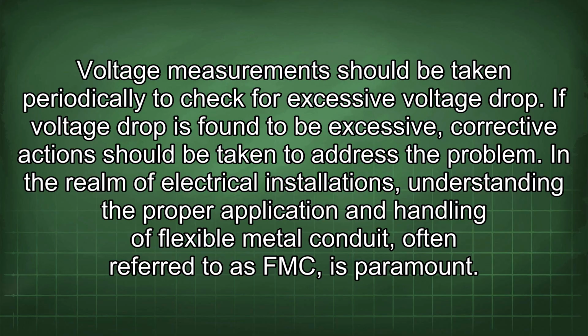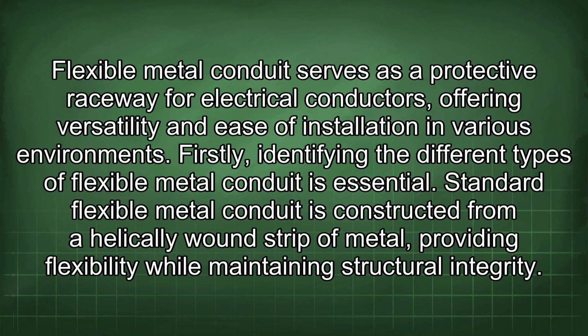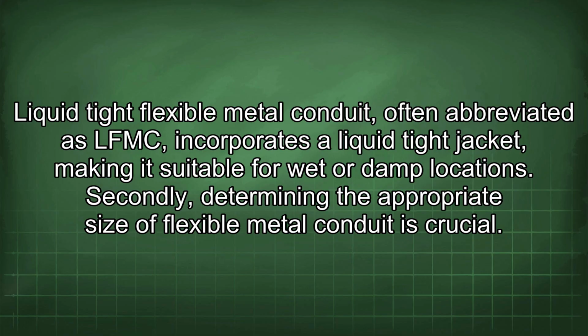In the realm of electrical installations, understanding the proper application and handling of flexible metal conduit, often referred to as FMC, is paramount. Flexible metal conduit serves as a protective raceway for electrical conductors, offering versatility and ease of installation in various environments. Firstly, identifying the different types of flexible metal conduit is essential. Standard flexible metal conduit is constructed from a helically wound strip of metal providing flexibility while maintaining structural integrity. Liquid-tight flexible metal conduit, often abbreviated as LFMC, incorporates a liquid-tight jacket, making it suitable for wet or damp locations.